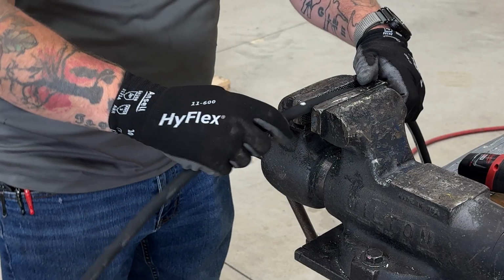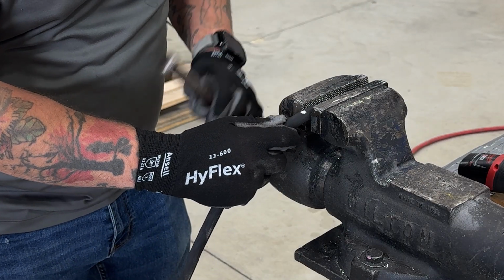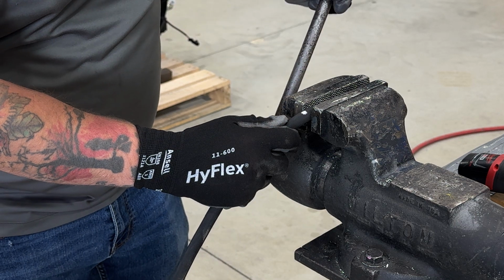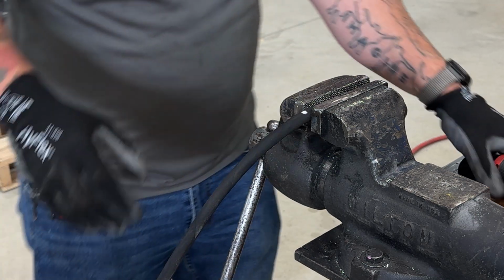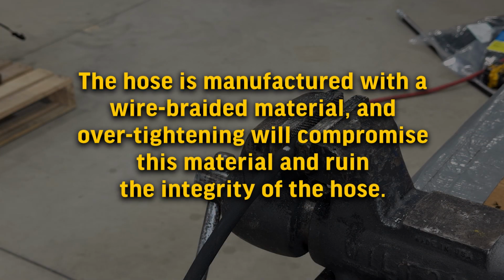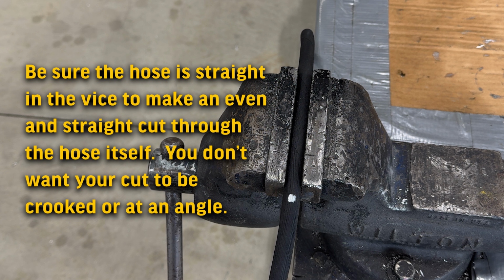Using a tool vise, place the marked hose close to the edge of the vise to secure the hose. Loosely secure the hose in the vise itself. The hose is manufactured with a wire-braided material, and over-tightening will compromise this material and ruin the integrity of the hose. Be sure the hose is straight in the vise to make an even and straight cut through the hose itself. You don't want your cut to be crooked or at an angle.